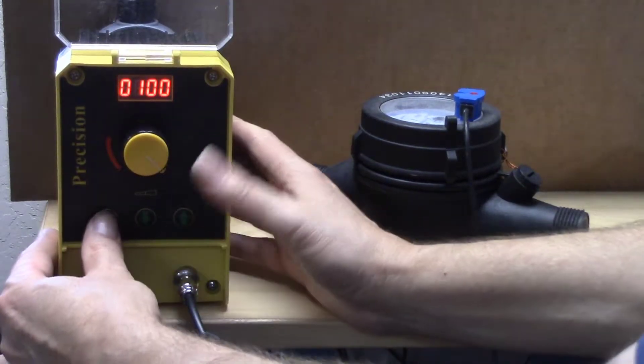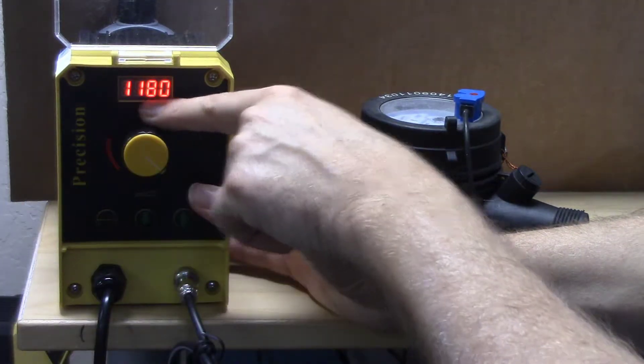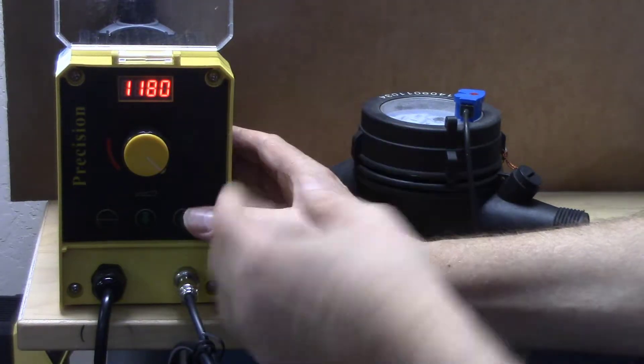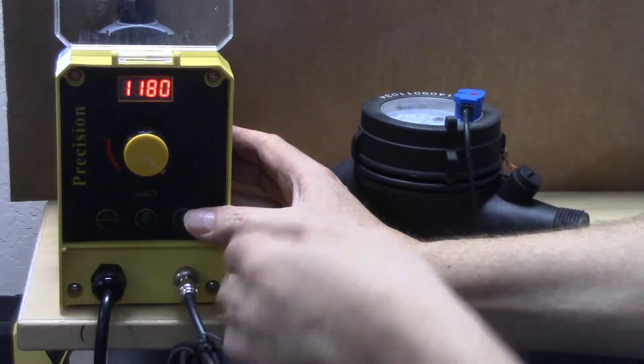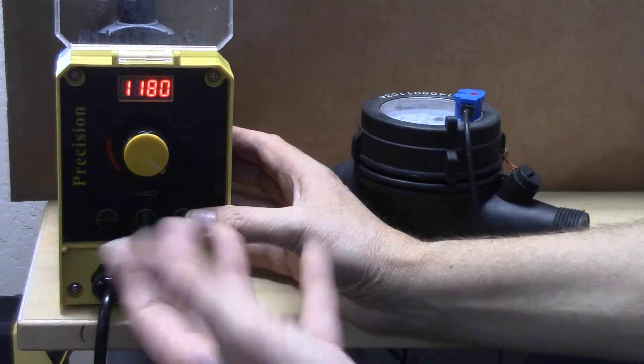Right now it's on 100%. Parameter one has to be set at 180—that's part of what makes it a 24-gallon-a-day pump. If you set it lower than 180, it will be less than a 24-gallon-a-day pump.